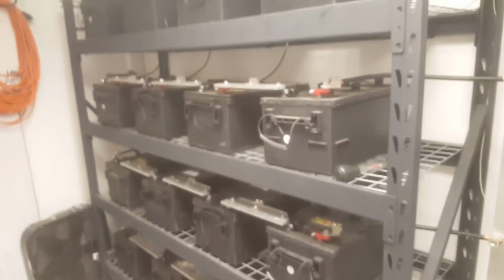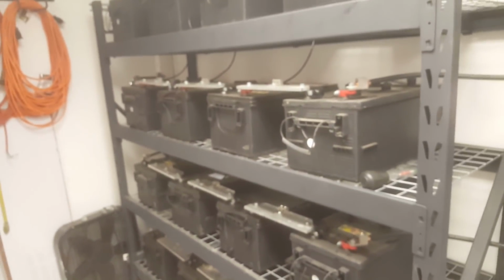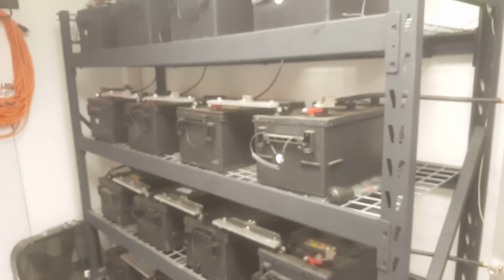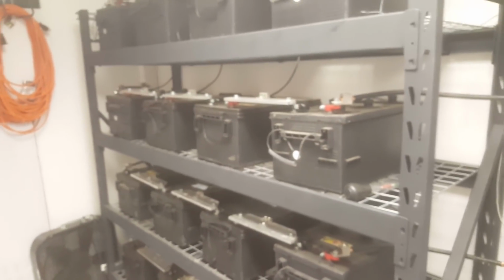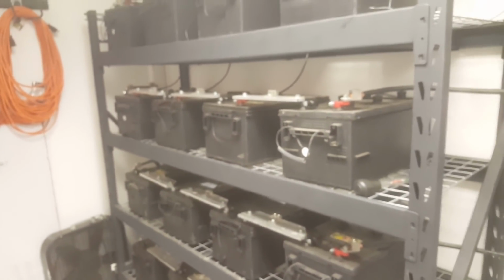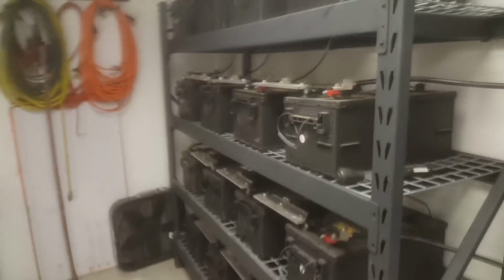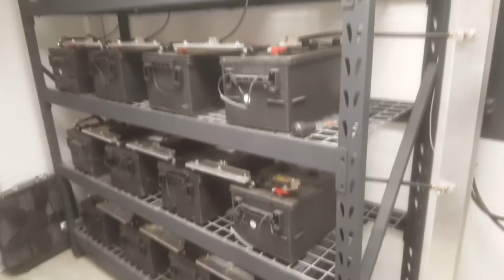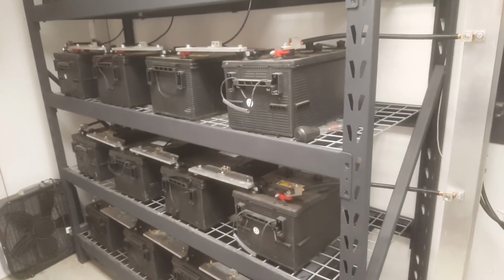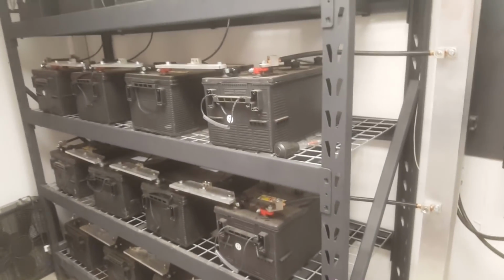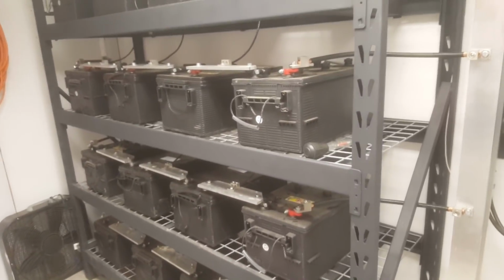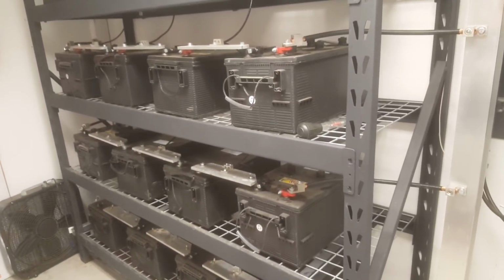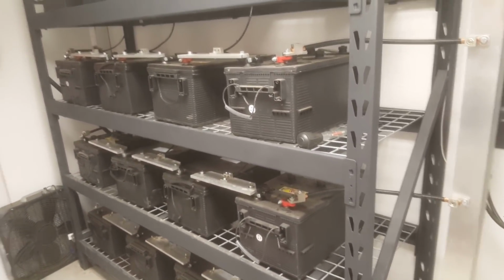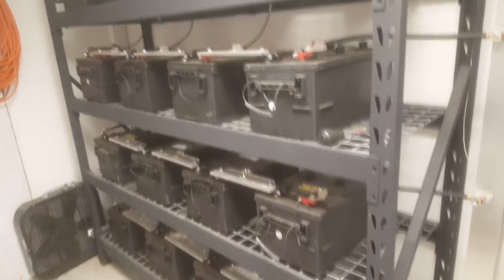And oftentimes if you have a cell that's getting hot, that means there's another cell that is not charging properly, and at that point I would pull the battery off the rack and put it on this other charger. That way that battery can go back to full operating condition, and then the other batteries aren't having to work harder because that one's working less. So if a battery's getting hot, that usually means something's wrong, and that means you need to check it out.